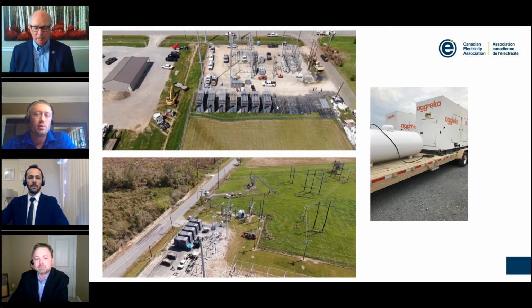We're running all sorts of different voltages: 240 delta with a high leg, 208 three-phase, 480 volt three-phase, 12470, 4160, maybe even some 24.9 kV in a couple spots. For storm response, we're generally feeding our utility customers directly at low voltage, and in some cases at medium voltage like 4160. In many cases we're providing electricity to a distribution line, or a section of it, that has been sufficiently repaired to accept electricity, while the transmission line—which is de-energized—is still being repaired.